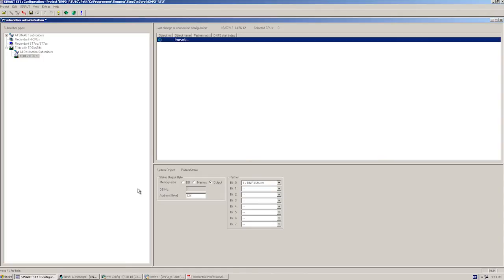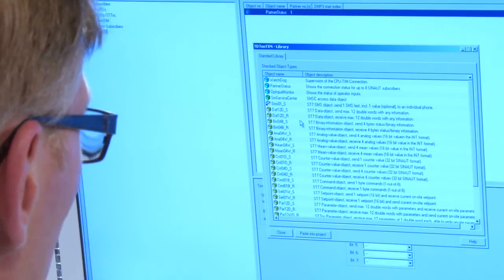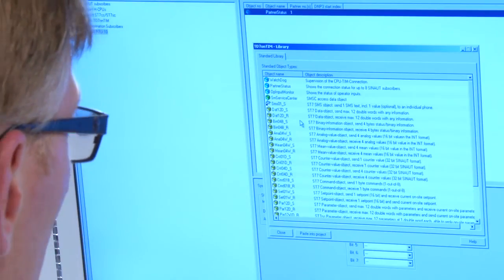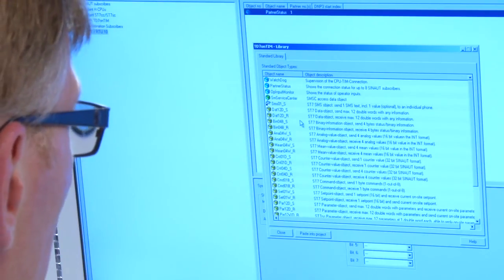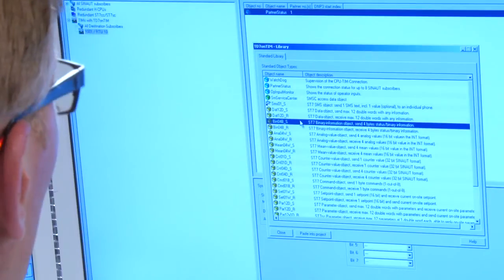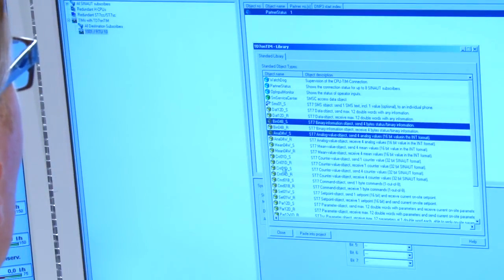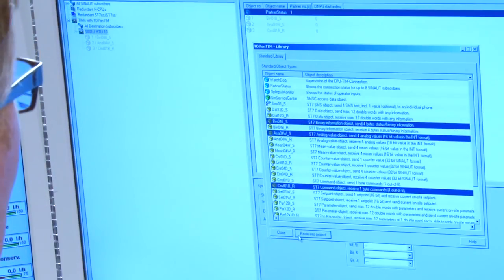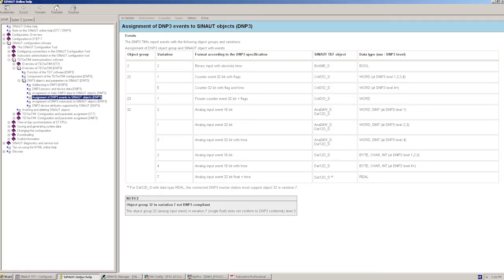Using this byte, the CPU can now monitor whether the connection to the master is OK or faulty. We want to transmit messages and analog values and receive commands. For this purpose, we select the three blocks BIN 04, ANA 04 and COMMAND 01. As evident from the online help, the BIN 04 block corresponds to DNP3 object group 1 or 2 and the ANA 04 block to object group 30 or 32.